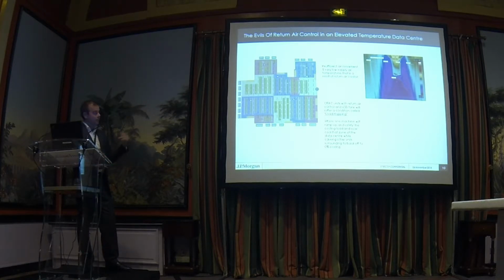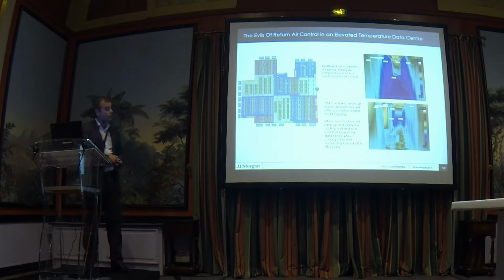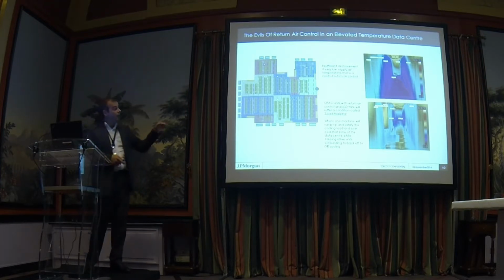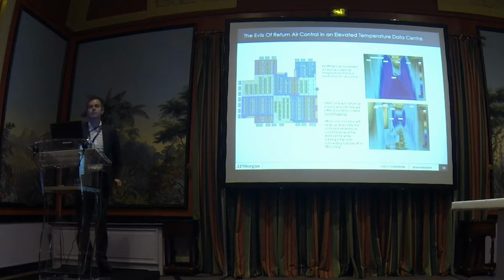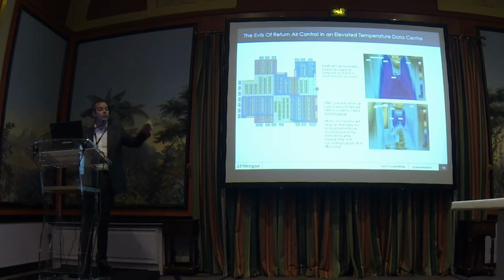But the next thing is it's too cold. That's the next issue we had. So we went through, and this is after we'd leveled all the floor tiles out, so they're all semi-closed, so to speak. But now you can see I've got the constant temperature all the way down until I get to about here. And this is where the evil of the return air control comes into it. That point there was a blade server right next to the CRAC unit, just absolutely flogging out hot air. And it was hitting the sensor and making the unit go 100%. This is why you get to a very dangerous condition where you have air conditioners all at a 24 degrees return air set point, and all of a sudden, yeah, let's do an efficiency thing, let's put them all up to 27. This load hopping and this overcooling, undercooling will become even worse, because the air conditioner's got more ability to bring the air temperature down from 27 to whatever is coming out the bottom than it has from 24. So you might find you have one doing all the work and then two next to it doing nothing.